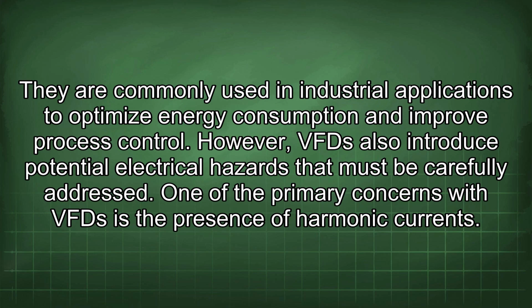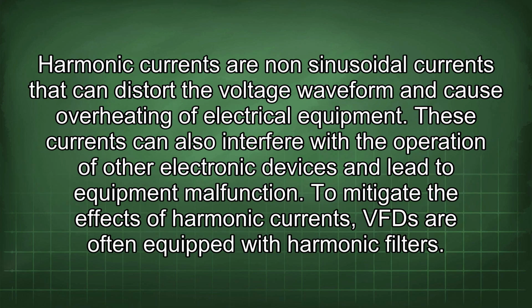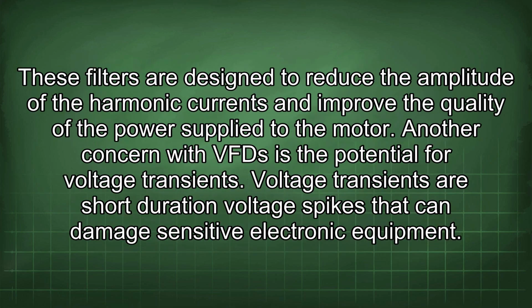One of the primary concerns with VFDs is the presence of harmonic currents. Harmonic currents are non-sinusoidal currents that can distort the voltage waveform and cause overheating of electrical equipment. These currents can also interfere with the operation of other electronic devices and lead to equipment malfunction. To mitigate the effects of harmonic currents, VFDs are often equipped with harmonic filters.